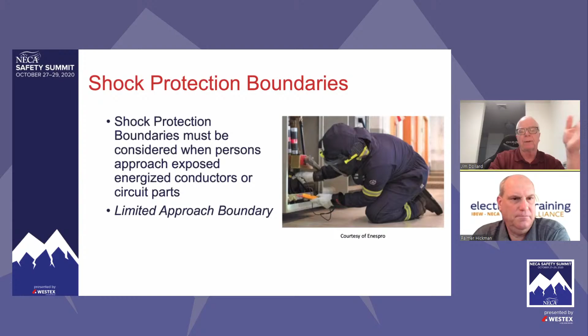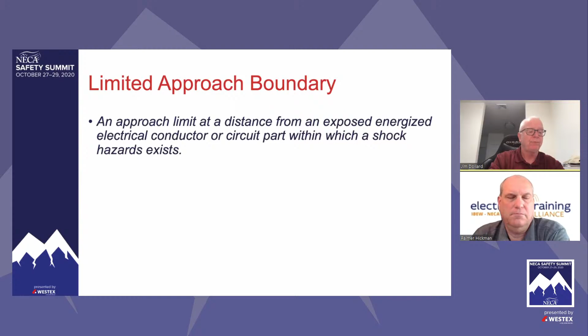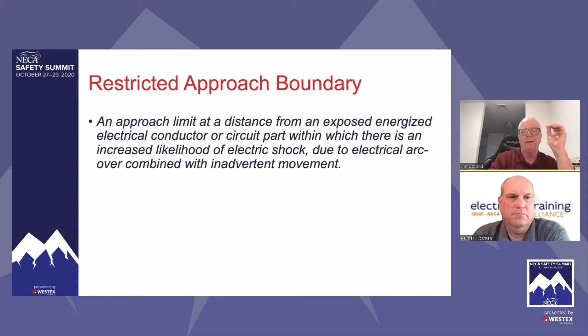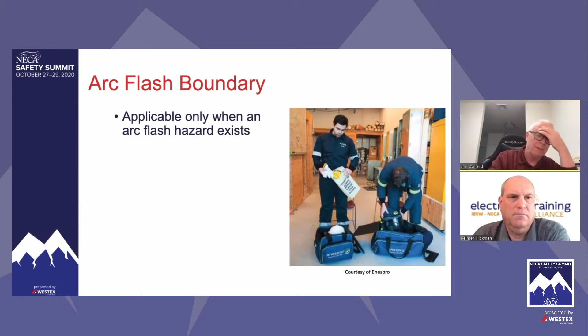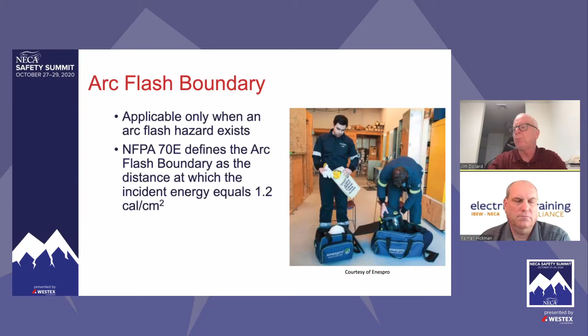And shock protection boundaries have to be considered, the limited approach boundary and restricted approach boundary. This is where something can occur. All right, that's what we're saying, that a hazard exists. So from 50 to 750 volts, it's going to be 3'6", and you're going to go into Table 130.4(D)(a) and (D)(b). Restricted approach, now we've got an elevated likelihood because now we're closer. There's an increased likelihood due to arc over combined with inadvertent movement. And again in 130.4, the arc flash boundary applies only when an arc flash hazard exists. If I've got a panelboard, nobody's working on it, it's all buttoned up, I don't have an arc flash hazard.